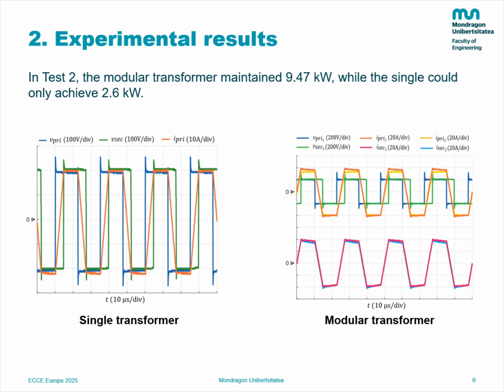This is achieved by manually placing in parallel the primary and secondary side ports of the modular transformers. This way, the equivalent inductance of the modular transformer is also nearly 3.6 times lower than the single transformer leakage inductance. In order to achieve a similar leakage inductance with a single transformer, a new transformer should be manufactured. The experimental waveforms of the single and modular transformer at test 2 are shown in the figures below.